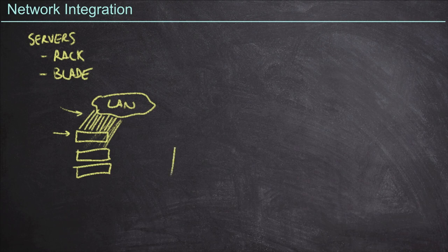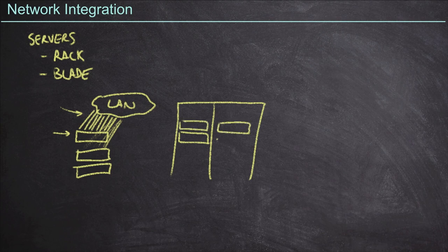Furthermore, if we were to draw this out physically, let's say we have a couple of racks right next to each other, and we deploy some rack servers in here, we deploy some rack servers in here, we have to decide how many top of rack switches we're going to have in our environment. This is always a debate, because if I have one top of rack switch up here and one top of rack switch over here, that's going to cause some amount of grief because I'm going to have to cable to both sides, which means my cables, even though I can logically draw it out like that, realistically my cables are going to have to go up into the tray, over and then down, or possibly down into the floor and over if we're using a raised floor.